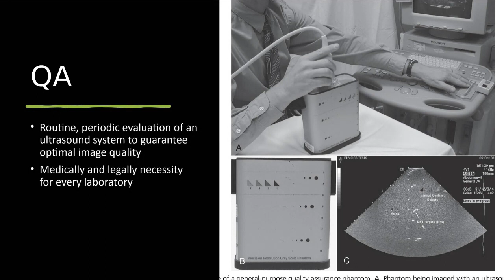So here are some of those phantoms that we're going to talk about. There are particular requirements and goals that any type of QA service has to abide by. The requirement of doing QA is that it is helpful for assessment of the system components. So when you have a physicist come in, they can say, oh, wait a minute, there's a crystal out on this transducer that is creating an artifact that maybe you guys didn't know about, right?